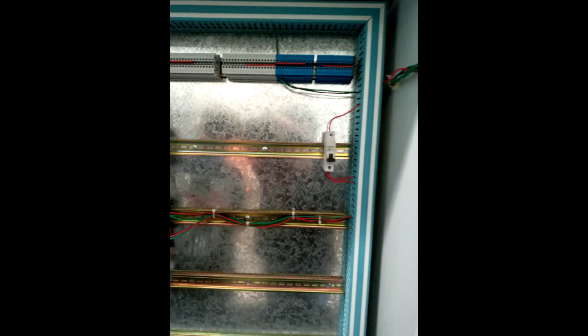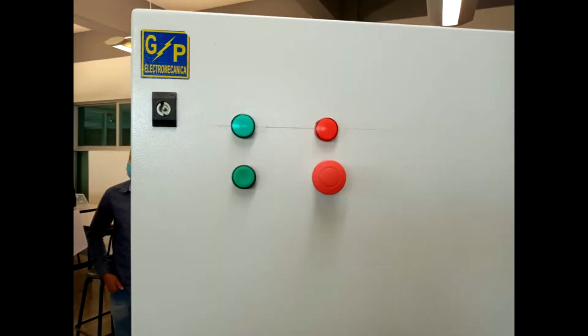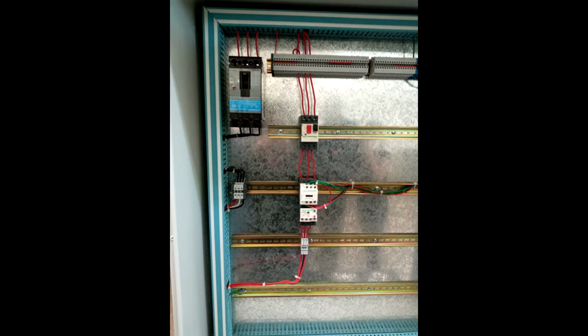The control section has a thermomagnetic switch as protection, two buttons and two lights that indicate whether the system is on or off. The functionality of the implementation was the following. The disconnector was turned on, then the thermomagnetic switch too. With that, the whole system was energized. Then the start button turned on the motor and the stop button stopped it.